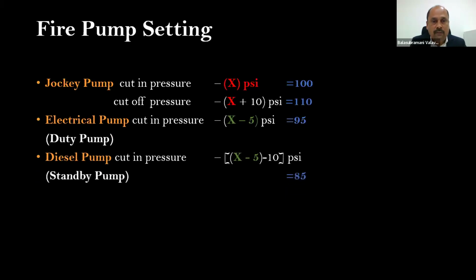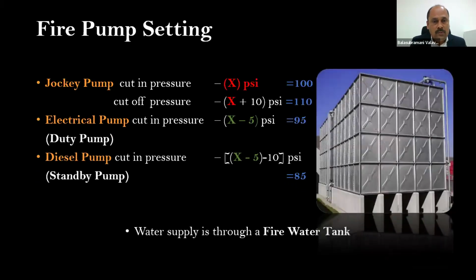When it reaches, say, 85, it runs automatically and allows the water to pour on the respective area. The water is supplied through a fire water tank. A sectional tank is used based on the NFPA standard, where you can have 20 minutes, 30 minutes, or 60 minutes. There are areas where a concrete tank is also provided for 60 minutes, where the capacity is more. This time, 20, 30 or 60 minutes, depends on the size, the requirement, the equipment, everything put together, the design, and then the tank size is finalized.